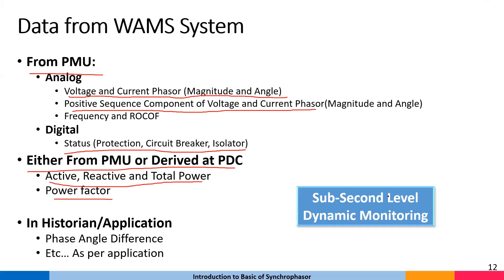This is why it provides a very good sample rate and a dynamic kind of scenario. In any power system, the reporting rate differs from the sampling rate. Sampling rate at the relay level is more than 2 kilohertz, because estimating a phasor needs a good number of samples within a 20 millisecond cycle. If you have fewer samples, the estimation becomes less accurate for protection or other purposes at the relay level.